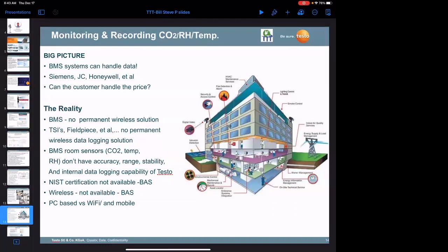They also take temperature sensor inputs from each room to control a VAV box, bring in supply air, and control reheat coils for warm air in the wintertime. But the problem is that BMS systems and their sensors are not data loggers. They're designed to measure and send an output to a control device, like a fan or a variable speed drive, something that changes to keep environmental conditions constant.